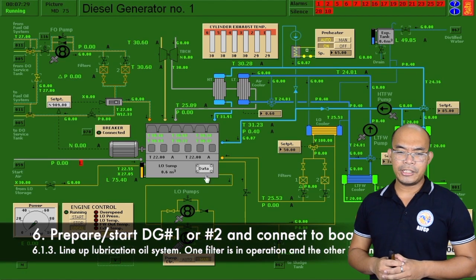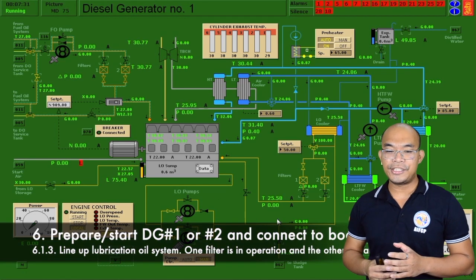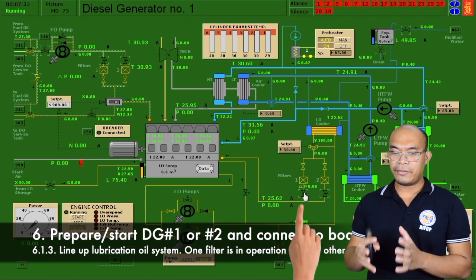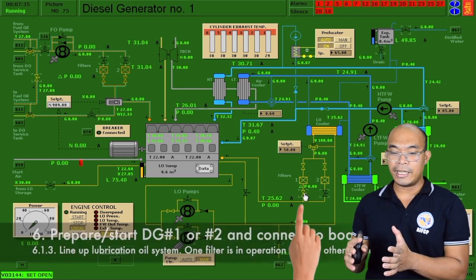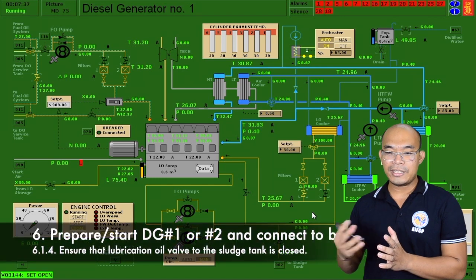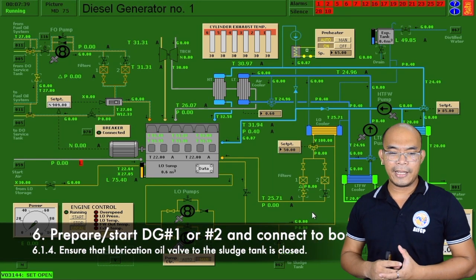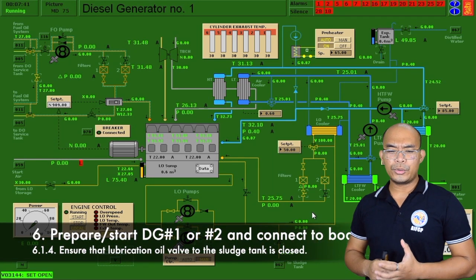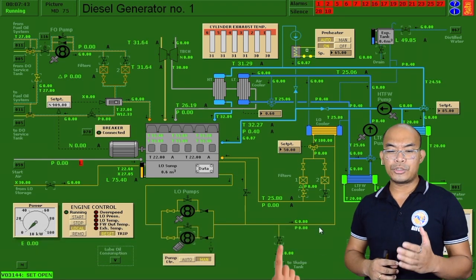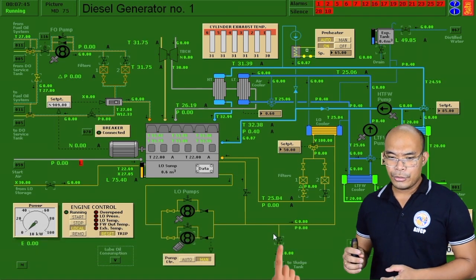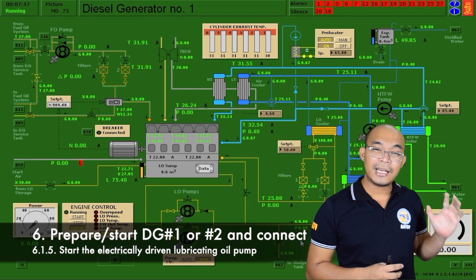Next step is we have to line up the lubrication oil system. So one filter, turn it on and open the valve, and the other one we just keep on standby. We also have to ensure that the lubricating oil valve to the sludge tank is closed, as we can see here, it should be closed.